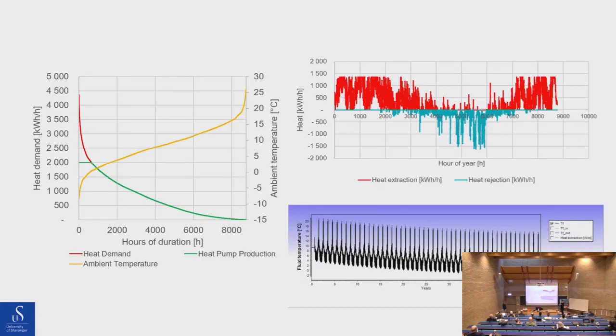So the undisturbed temperature in the ground, the average at 300 meters, is about 10 degrees. Then when we begin to extract energy, the temperature quite quickly drops to 4 degrees, and then it goes slowly down to about 0 degrees average temperature in year 50.